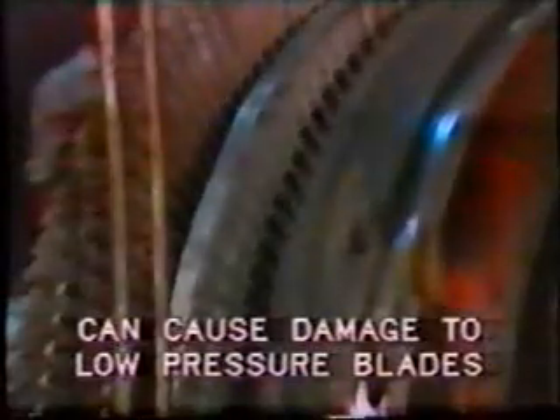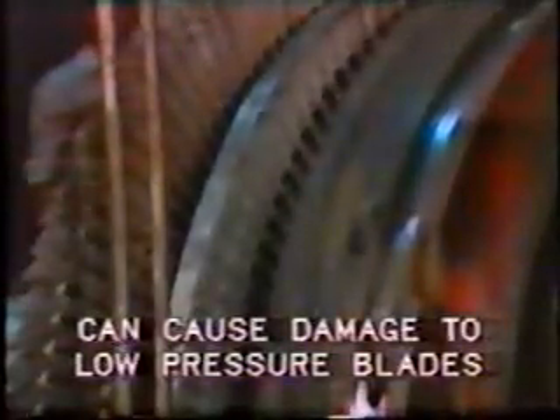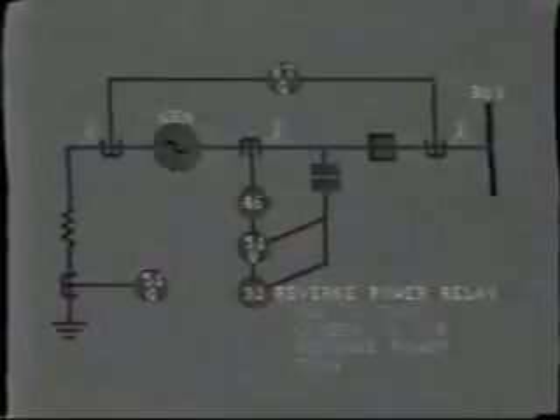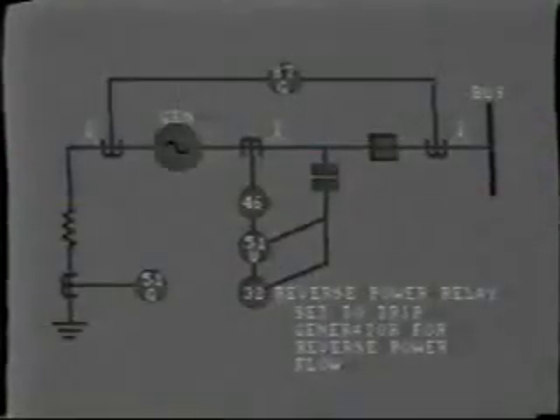In this situation, the turbine is no longer driving the generator, but the generator is still synchronized to the power system and so draws current in an attempt to drive the turbine. This situation can cause serious overheating and damage to the turbine low-pressure blades. Typically, the reverse power relay is set to operate and trip the generator if reverse power flow is more than 0.5% of rated power for 10 seconds or more.